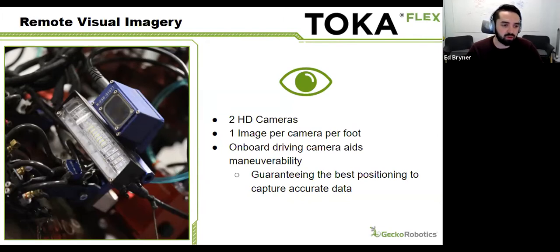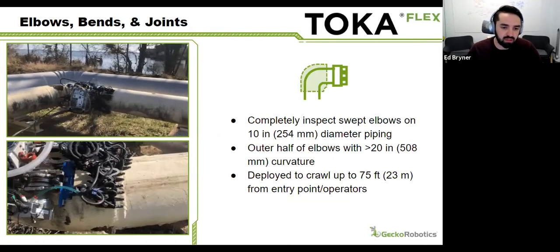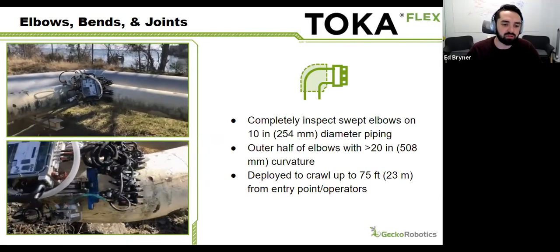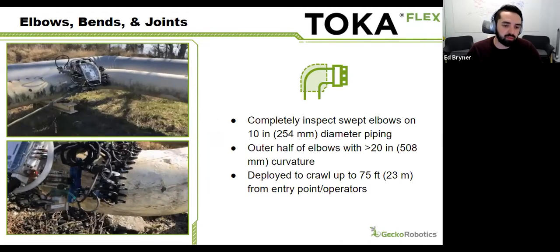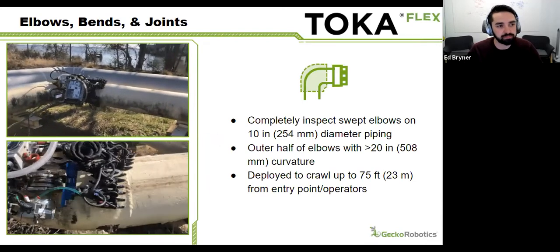And that was picked for a reason, that we're performing these automated inspections. And so I think we quote a couple of cleanliness standards that we generally like to see for the most robust and reliable inspection. But as you saw in the last frame, the surface was not perfect. Some of the actual coating here is chipping away or degrading over time due to weather and other factors. And we were able to collect a very robust data set even on an asset such as this.